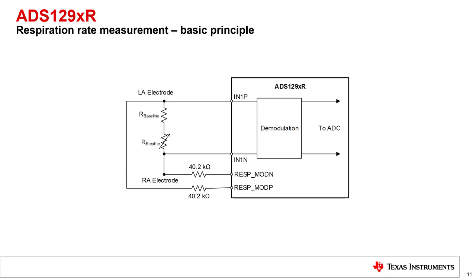In this diagram, we are modeling the patient by a combination of a constant impedance, R baseline, and a changing impedance, R breathe. R baseline is a constant value ranging between a few hundred ohms to a few thousand ohms. R breathe corresponds to the change in the body's impedance as the thoracic cavity expands and contracts.